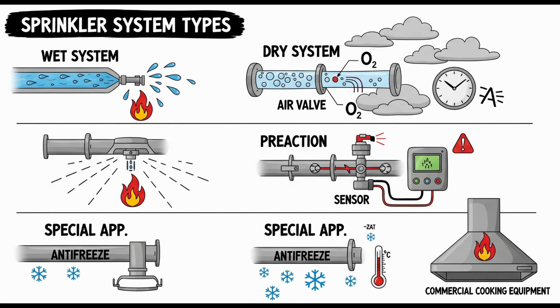Another practical rule. The main control valve used for operational testing of a refrigerated space sprinkler system must be an indicating type valve located on each sprinkler riser outside of the refrigerated space. Test valve in the warm area. Yes. This allows maintenance personnel to perform necessary system tests like trip tests or flow tests from the relative comfort and safety of the warm area, without having to enter the freezing environment unnecessarily just to operate a critical test valve. That makes a lot of sense for practicality and worker safety, less time spent in sub-zero conditions.